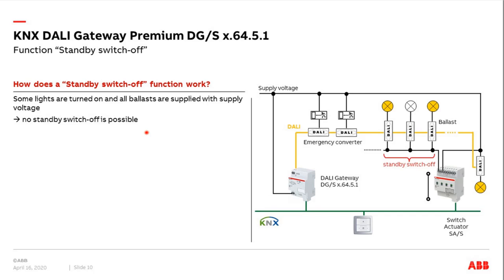How does the standby switch-off function work? The DALI gateway is permanently connected to its supply voltage — we do not switch off the supply voltage for the DALI gateway. On the output, we connect DALI emergency converters, device type 0 ballasts, and device type 8 ballasts. All the supply voltage for these ballasts is later switched off via a switch actuator. Some other ballasts can remain permanently connected to supply voltage and not be part of the standby switch-off function.